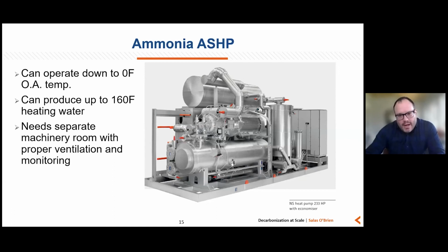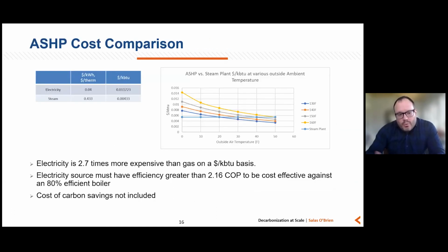I think an important thing to consider, though, as you look at air source heat pumps, is that their coefficient of performance needs to be relatively high if you're going to compare them from a cost effectiveness perspective on a dollar per kBtu basis with a gas boiler. So, this is an illustration based on the work we did at University of Miami in Ohio, using their utility rates and that system specifically. But it is really important, like the previous analysis showed, to look at the outside air temperature, at what kind of production temperature you're trying to make on the hot water side, and really what that balance point is on the outside air temperature and where you want to select and operate your equipment long term.